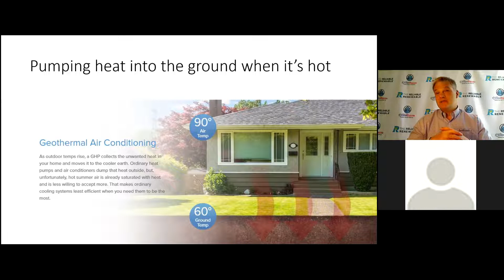But what we're finding in places like Phoenix is that conventional refrigerants are starting to not function at 120, 125 degrees. We're losing capability to cool homes with air conditioners, which, already at 105 degrees, are only operating at about half their capacity. So 60-degree dirt looks pretty good to a house you're trying to keep at 70 degrees. That's a much easier place to put your heat.